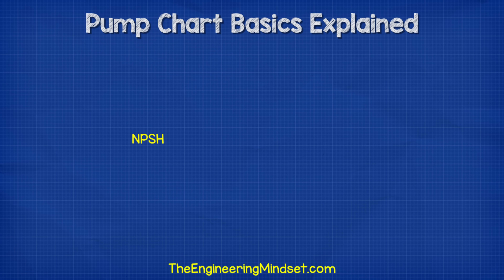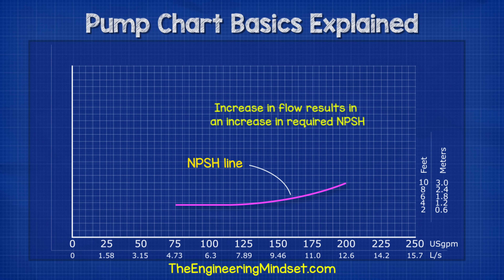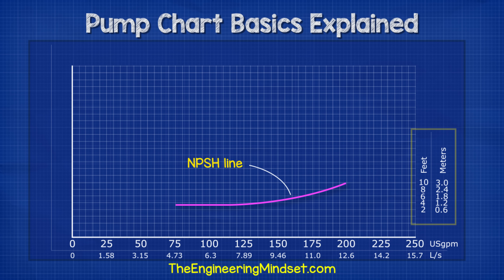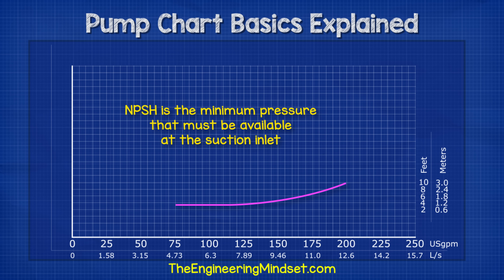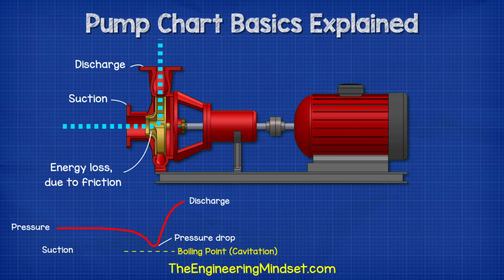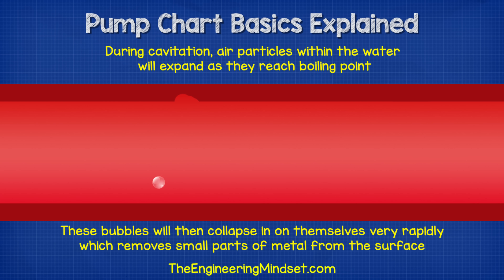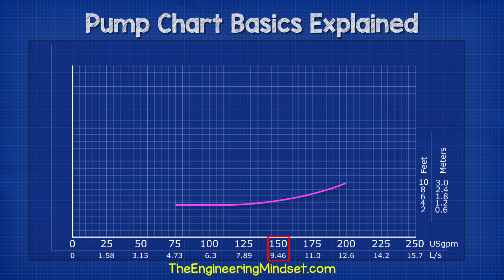NPSH — this is the required NPSH, or net positive suction head pressure. This usually has an upward curve, which means as the pump flow rate increases, we see the NPSH value also increases. We measure this in meters or feet, sometimes kilopascals. The NPSH is the minimum pressure that must be available at the suction inlet of the pump to overcome the entrance losses and avoid cavitation. The available pressure at the inlet must therefore be greater than this value. Pump cavitation is where the pressure at the inlet of the pump reaches a low enough point that the water begins to boil, creating rapidly expanding and collapsing air bubbles which will gradually destroy the surface of the pump and the casing. For this example, if we were to move 150 gallons per minute, then we would require an NPSH value of around 4.9 feet.